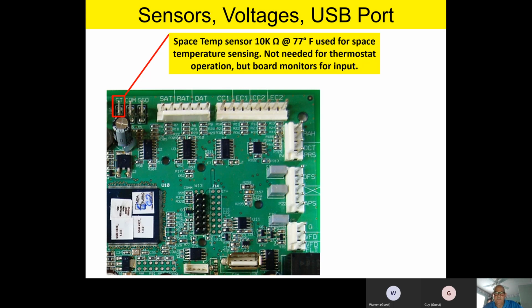Now, that space temperature sensor is going to be used for sensing space temperature. It should be noted that the space temperature sensor is not needed for thermostat operation. However, the board still monitors and looks for an input on ST. So sometimes, especially on older equipment, even though you're on a thermostat, which has nothing to do with the unit operation, if it cannot see a space temperature sensor, it'll flash a little code and say space temperature sensor unreliable or something like that. Even though the unit's working perfectly fine, you'll have this little light flashing and the display saying it can't see space temperature. And of course, the technician's first thought is, oh, there's something wrong with the equipment.